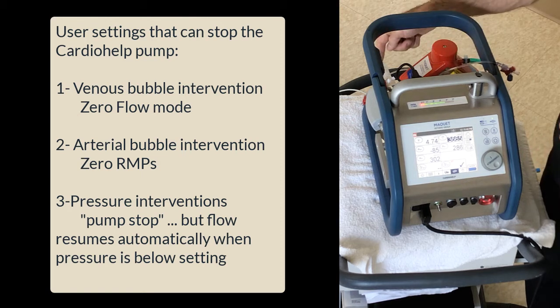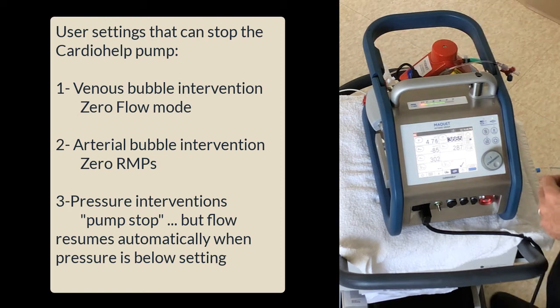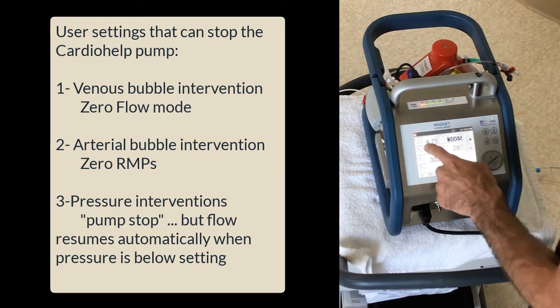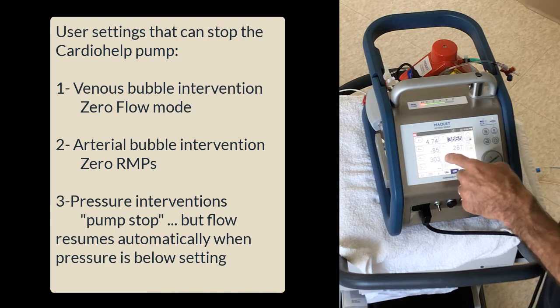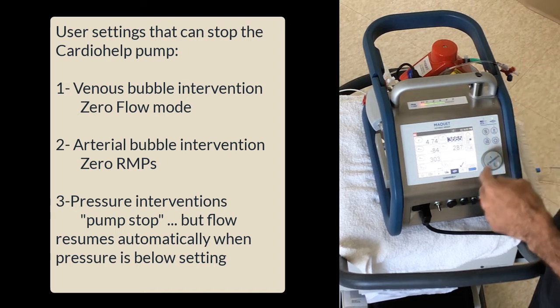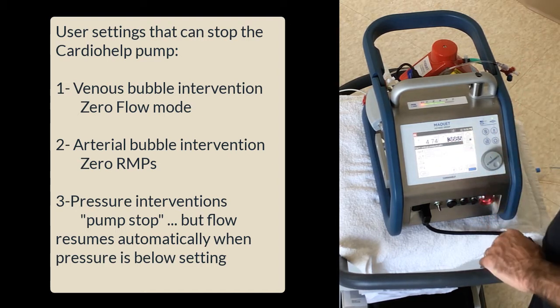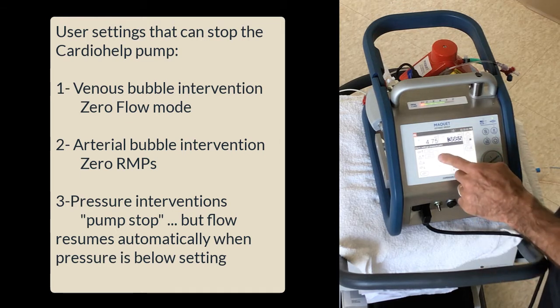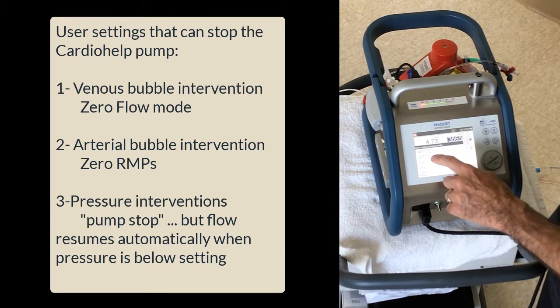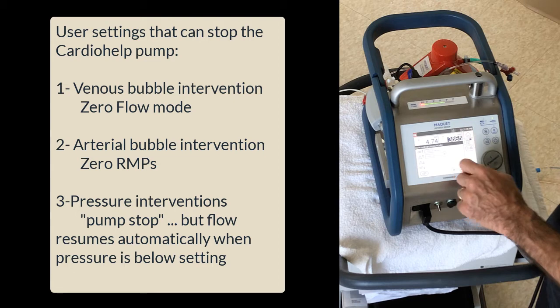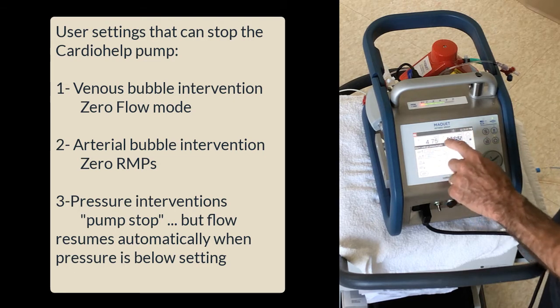So, bubbles, venous bubbles, arterial bubbles, they can stop the pump. Pressures can stop the pump. There are 3 pressure settings here: the venous, the arterial, and the internal. They all have 2 limits you can set. Let's go into the P-art. You can see you can set a limit for when you want an audible alarm. Right now it's set to 400. And when do you want the pump to stop? 500.